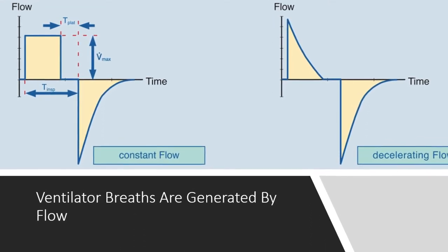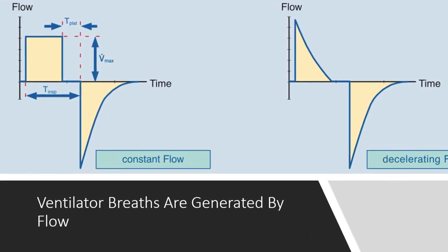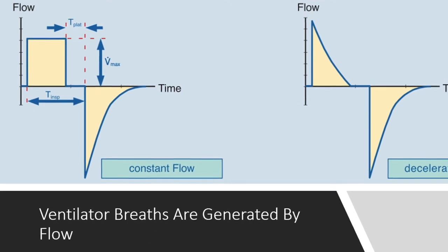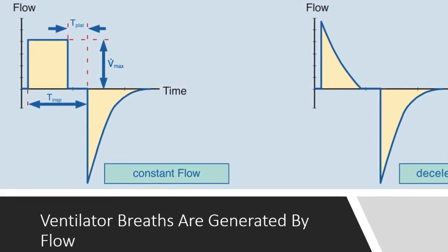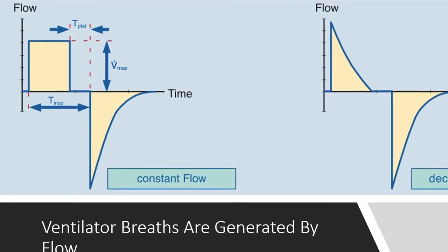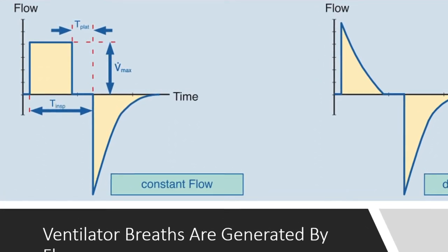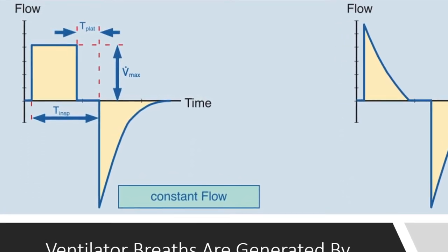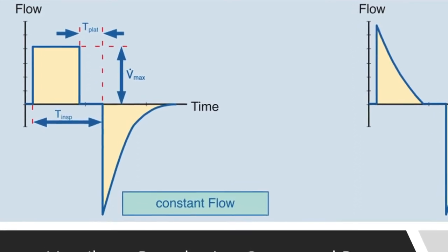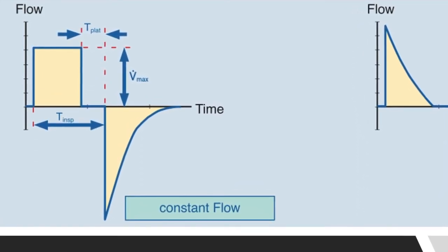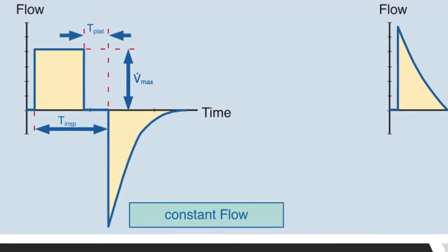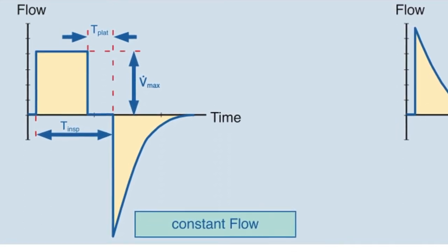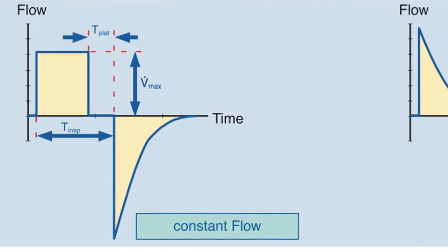Starting with the volume-style breath: there is no flow at the start, then we go into inspiration. During a volume breath, you get a constant flow throughout inspiration — a constant flow until the set target volume is reached, after which no more flow continues but we're still in inspiration. Then we cycle into expiration, the patient expires, you get reverse flow, which then diminishes back to zero waiting for the next breath.